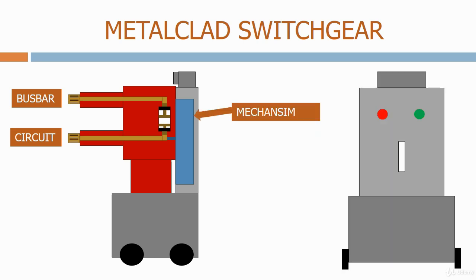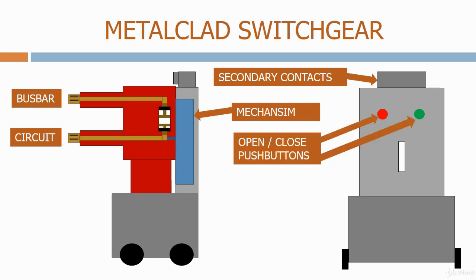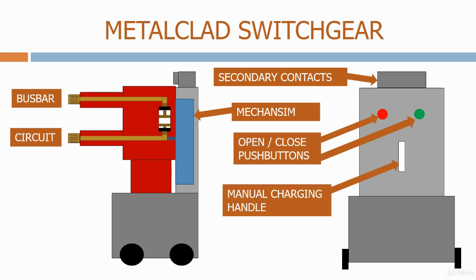To operate the vacuum bottle, we have a spring-loaded mechanism, which ensures that the circuit breaker contacts open quickly and to a defined distance. At the top of the truck, we have the secondary contacts. These carry all of the trip, close, and alarm contacts from the truck to the main enclosure. We have the manual open and close push buttons, which allow the operator to change the status of the circuit breaker whilst it's in the housing. And finally, we have the manual charging handle. This allows the operator to charge the mechanism's springs when the main power supply has failed.